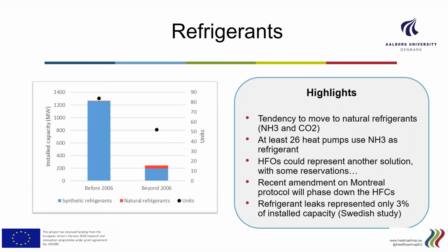I mentioned the hydrofluoroolefins, and this is a synthetic refrigerant, also known as the fourth generation of refrigerants. They're similar to the hydrofluorocarbons I mentioned earlier, as they contain hydrogen, fluorine, and carbon atoms. But unlike the hydrofluorocarbons, they have a global warming potential of only 4. They are a possible replacement for the hydrofluorocarbons due to their similar thermodynamic properties that allow the application of large-scale heat pumps, such as the ones built in Sweden in the 1980s, but they generally have a reduced efficiency compared to the hydrofluorocarbons. Moreover, these refrigerants are contested in some circles because of the toxic substances they release in case of leaks and after their breakdown in the atmosphere.